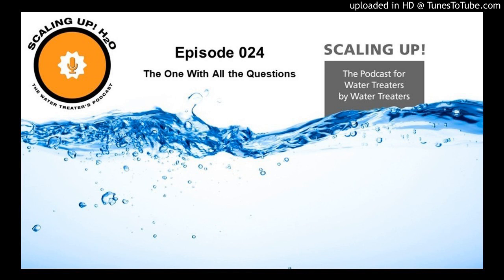Then you just have to remember whatever you diluted it to, you've got to add that back. So if it was normally a 20 mil sample and you couldn't run it because of the interference, you brought it up to half and half. So 10 DI water, 10 system water, and tested it then. Whatever you tested for, you'd have to multiply back by 2 because you're only testing half of what's really there.